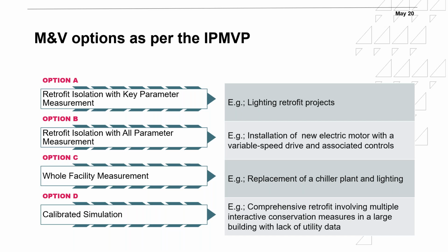Why is that? I have the lighting, let's say, in a building, and I change that to higher efficacy fixtures, let's say LEDs. I need to measure the LED consumption after the retrofit, and also I need to measure before the retrofit, whatever type of lighting I had, incandescent or fluorescent, whatever. I need to measure their consumption, and then I need to measure the consumption after the retrofit. The key parameter measurement is the consumption. I cannot really use the data from the cut sheets from the supplier. No, that's not acceptable. It's the key parameter that I need to measure. In lighting, normally for the hours, I can do a measurement on the hours before the retrofit, and then I can assume that it's going to use the same hours after the retrofit. However, for the energy consumption, I need to measure before and after. If the key parameter measurement is the power consumption, I would measure before and after.